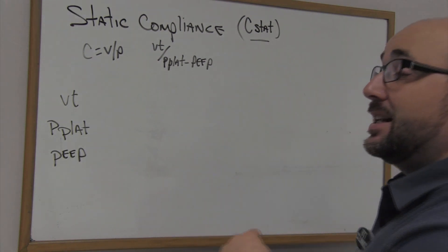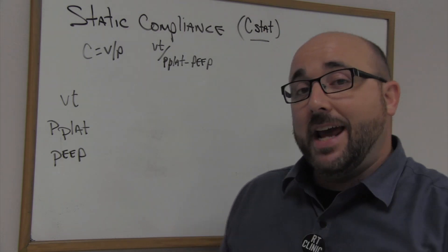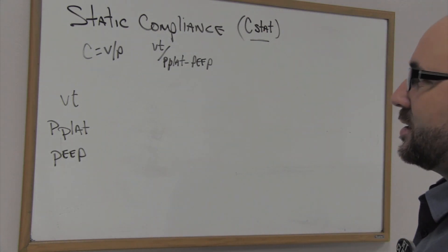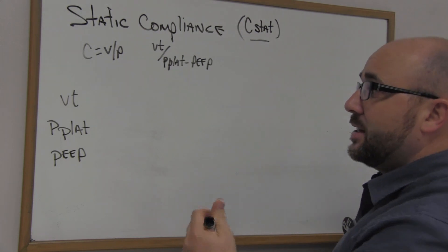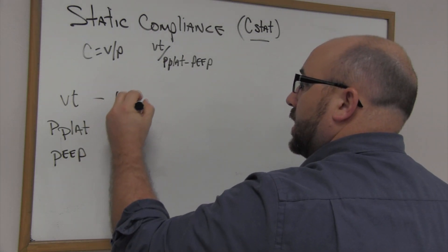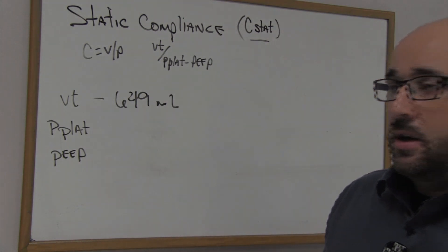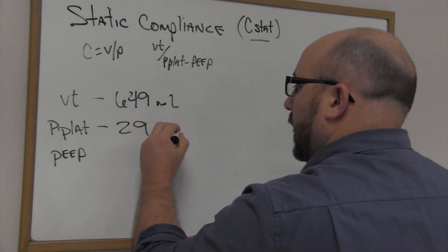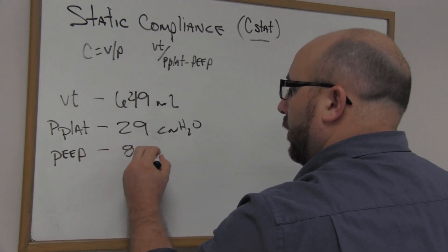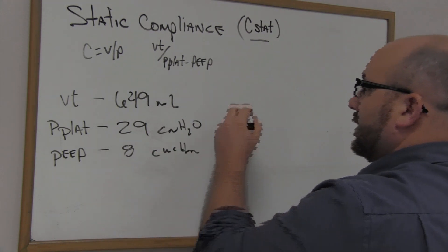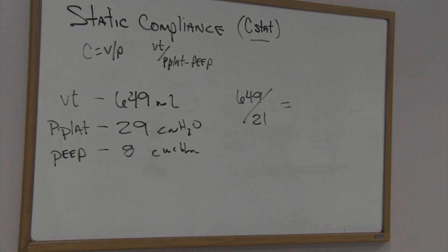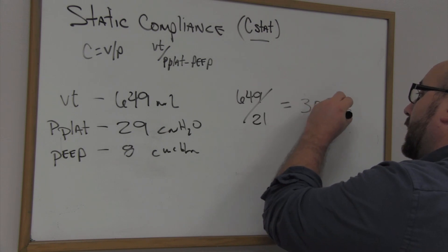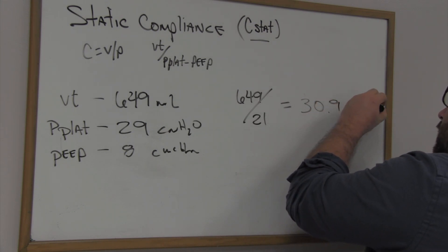For static compliance, the formula is: C-stat = tidal volume ÷ (plateau pressure − PEEP). For dynamic compliance it's tidal volume ÷ (PIP − PEEP), giving a bigger denominator and therefore a different value. Dynamic compliance can change quite a bit. On my test lung, I had a tidal volume of 649 mL, a plateau pressure of 29 cmH₂O, and a PEEP of 8 cmH₂O.